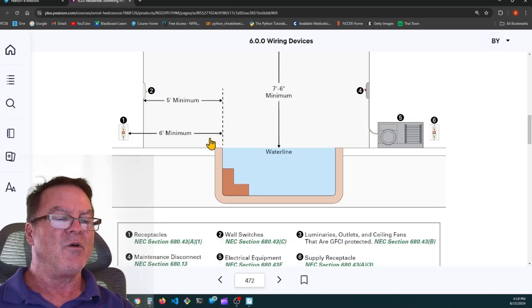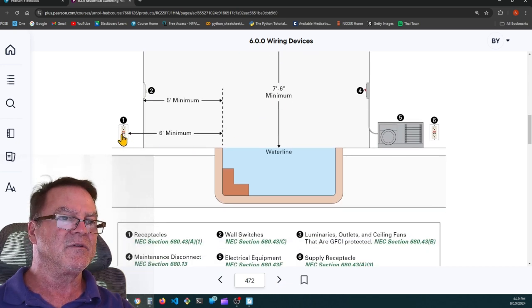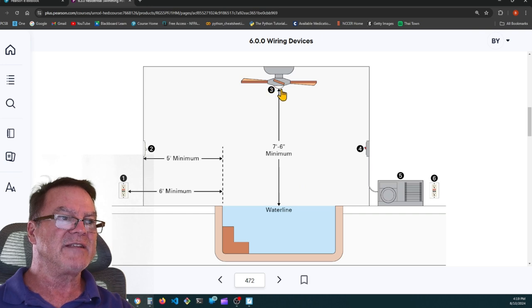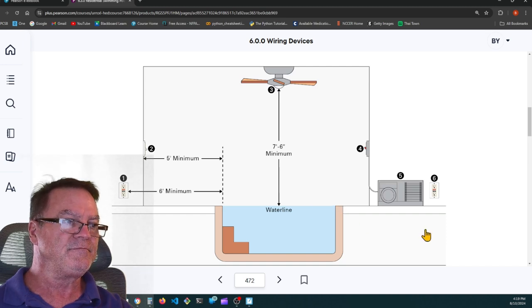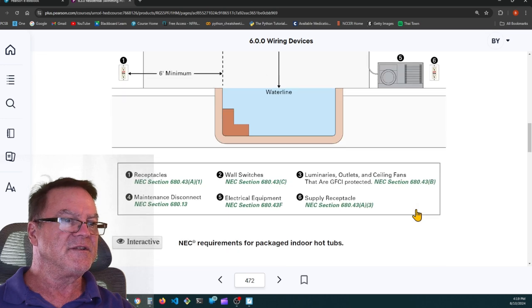Let's see here. So you have to have a receptacle no closer than 6 feet, and I think no further than, I want to say 10 feet. It might be 20 feet from the inside wall of the pool. It has to be a minimum of 5 feet away from a switch on a wall. If you have floodlights or a switch on your house, your pool has to be a minimum of 5 feet away from it. Paddle fans and lights have to be a minimum of 7 foot 6 inches above the highest water level. Let's see what else it says here.